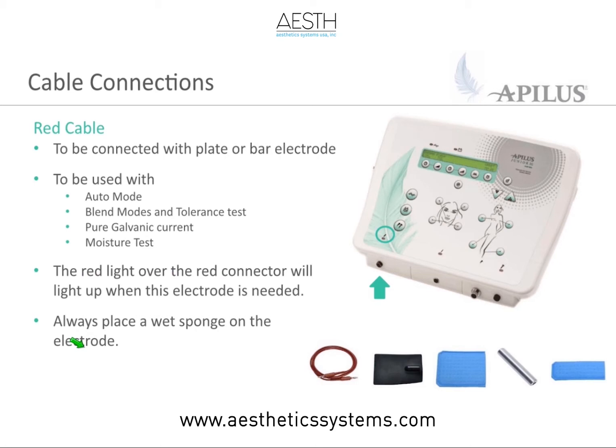You do need to place some sort of wet sponge, a wet paper towel, or any type of wet cloth over the electrode ground itself to facilitate the connection. So the red cord here could come with a few different accessories. The rubber plate is one thing. You can use that to place it, let's say, underneath a client's shoulder as opposed to having them hold the electrode. The rod is the stainless steel rod that can also be connected to the red cord. These may have come with your machine and they are just sponges. So like I said, you can also use something like a paper towel, but wetting something like that, you can slip the electrode right inside of it. It's like a little pocket and they fit over the electrode that it comes with.